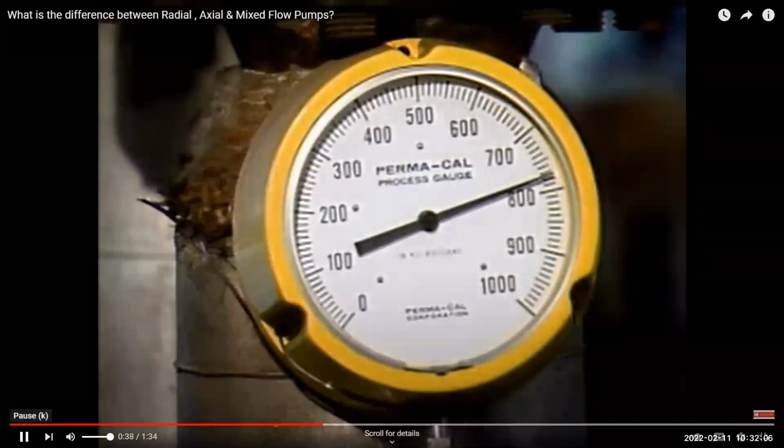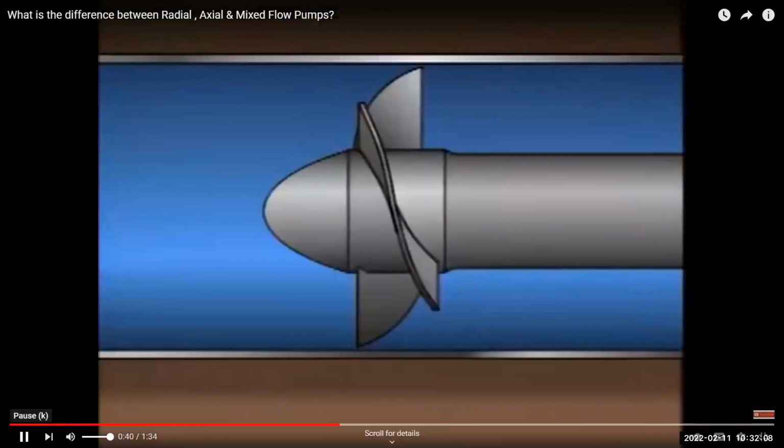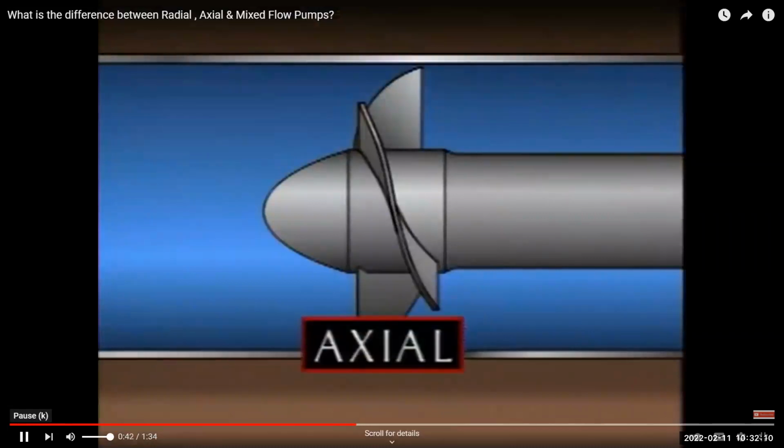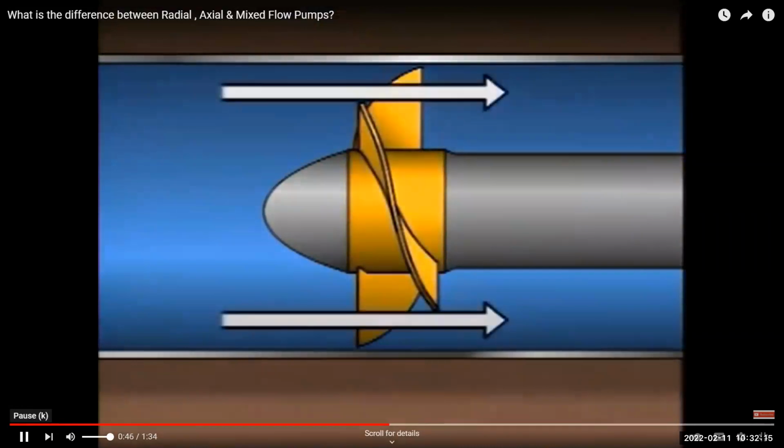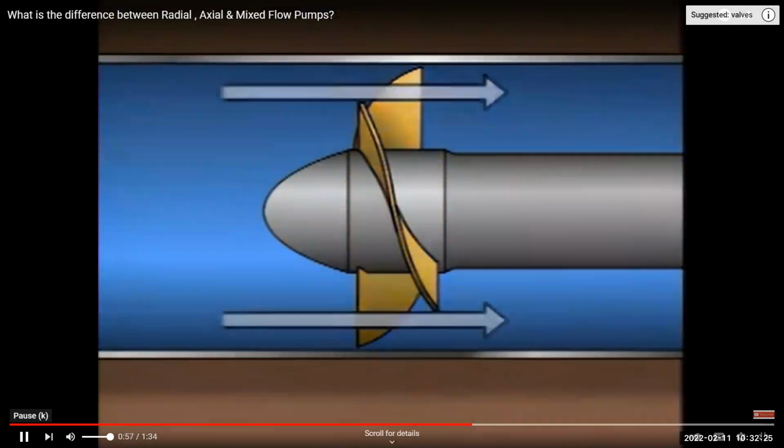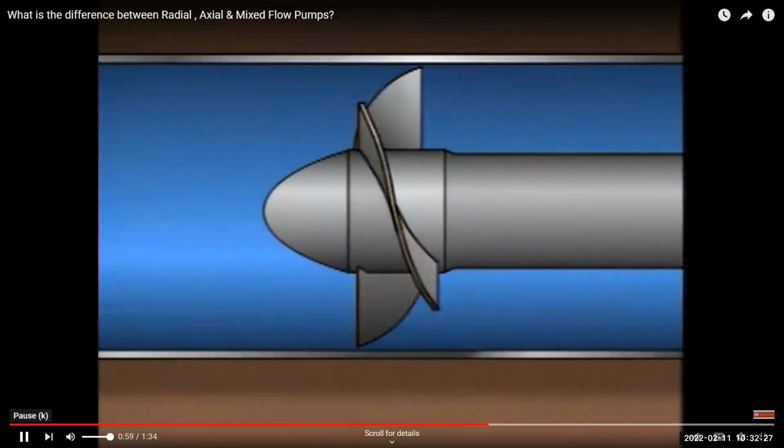Much liquid as other types of centrifugal pumps. In centrifugal pumps that have an axial flow design, the impeller moves the liquid through the pump along a path that's parallel to the pump shaft. In this type of pump, the liquid is moved mainly by the propeller action of the impeller's vanes. This impeller uses only a small amount of centrifugal force to move the liquid.